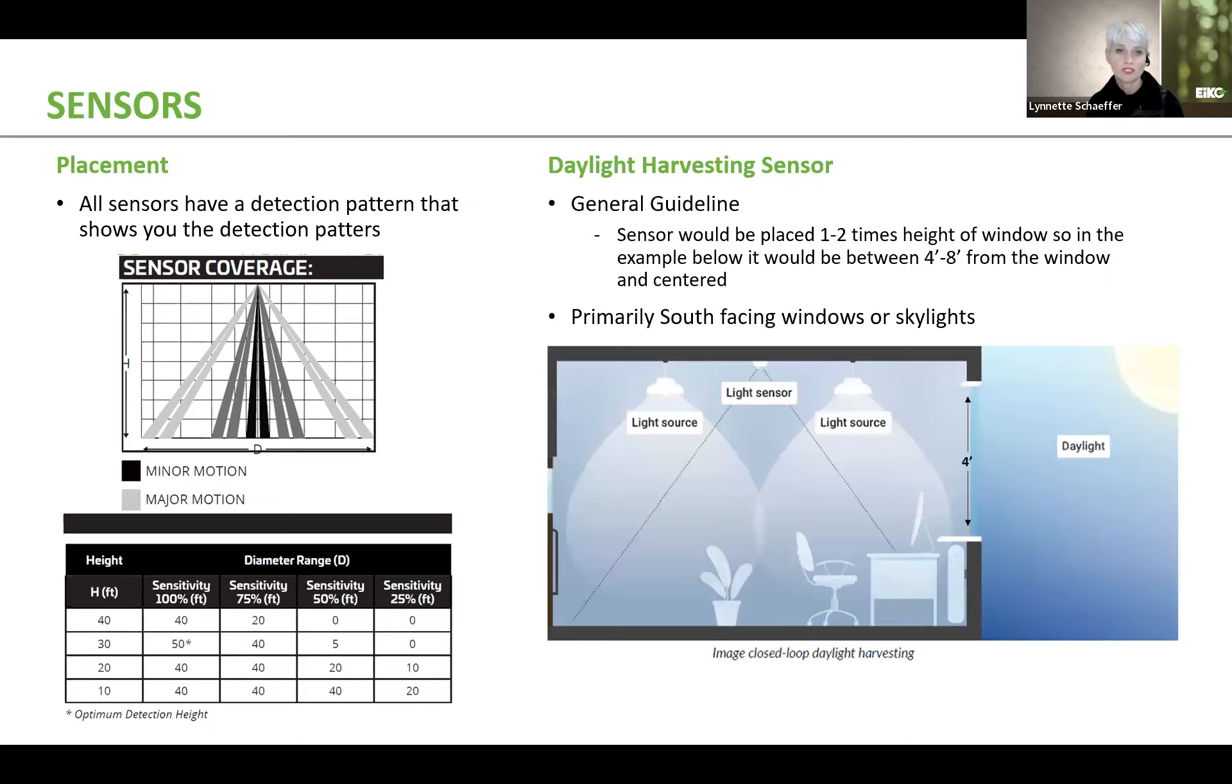Also, specifically for daylight harvesting sensors, these are usually used with anywhere where you have windows that are facing the south or maybe skylights. And a general rule of thumb is that the daylight sensor should be placed one to two times the height of the window. So in this example here, it would be between four feet to eight feet from the window and then centered in the space. That's a really good rule of thumb because you want to make sure you don't have that daylight sensor too close to the window. If you do, then you're not going to get that natural daylight coming in. You've got to make sure you get that back far enough to have that natural daylight coming in and have it be able to pick it up.